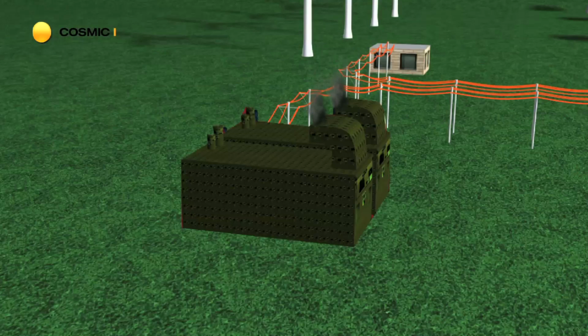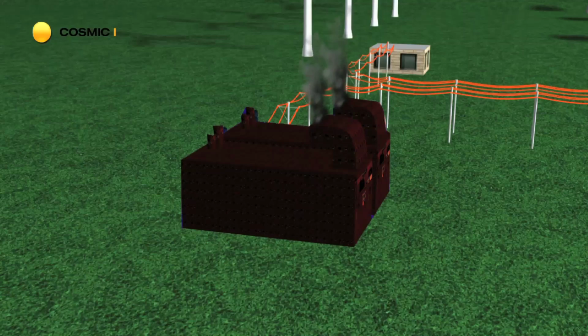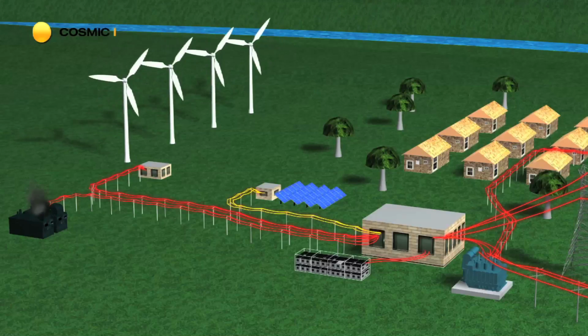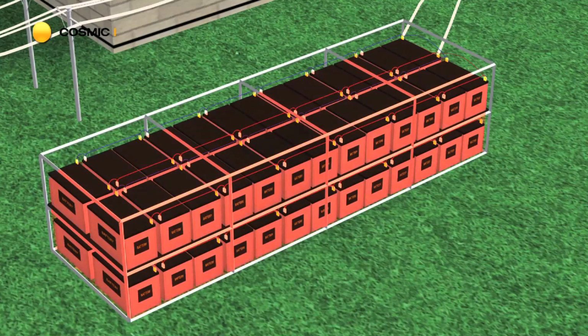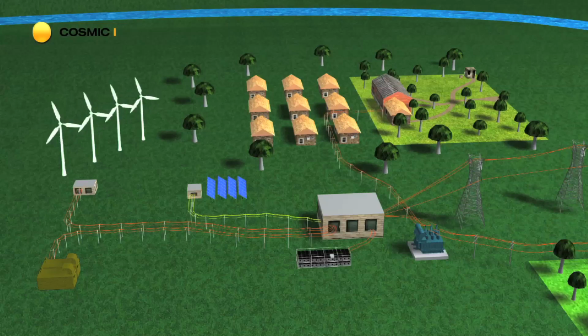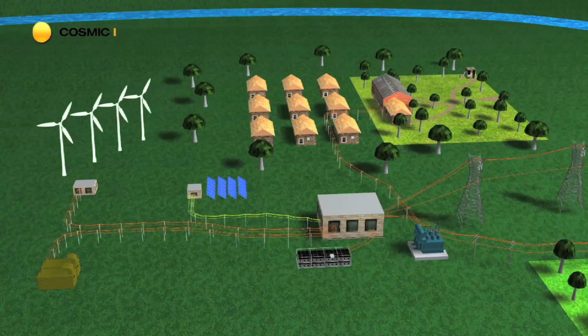In order to eliminate these costs associated with ramping diesel generators, microgrids can utilize battery-based quick-response energy storage systems. These systems can store energy when demand is lower than supply and deliver real and reactive power to the microgrid when demand is higher than supply.